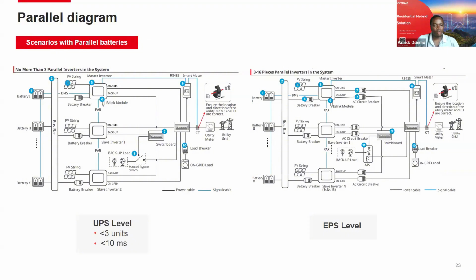Mark you, only one inverter will be communicating to the BMS, and the inverter connected to the BMS of the battery is actually the master inverter that will also be controlling the rest of the inverters in the daisy chain. The master is the inverter where you plug in a special dongle or communication module called the Ezlink module. Once that is plugged in, that inverter automatically becomes the master, and the rest become slaves reporting to the master inverter. The master inverter similarly monitors the incoming grid line using the CTs or the smart meter, to prevent export or to check how much you're consuming from the grid itself.